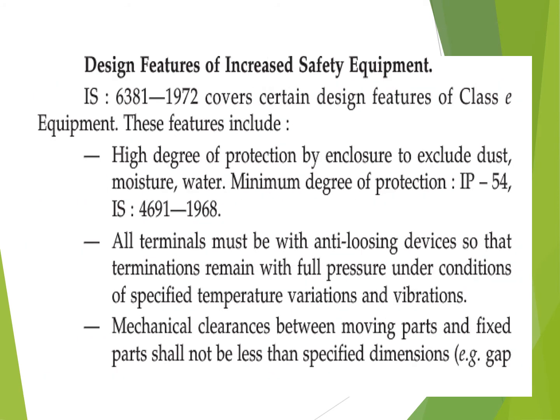The design features of increased safety equipment, that is Class e equipment, include a high degree of protection by enclosure to exclude dust, moisture, and water. All terminals must have an anti-loosening device. There will always be a problem with the terminal: a loose connection. There is always a chance of a spark, which can be avoided by this.